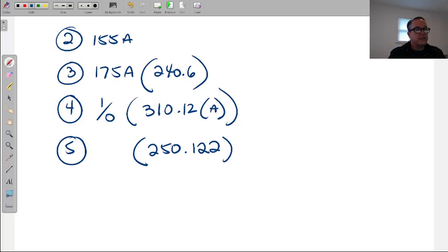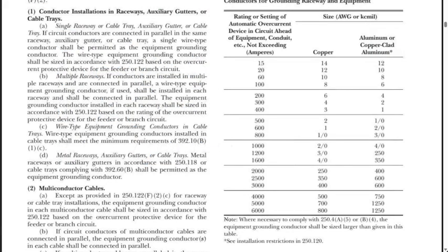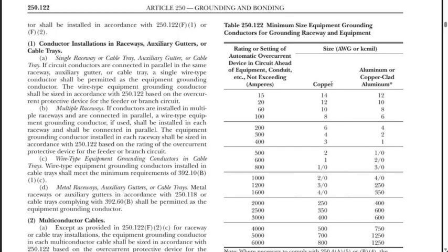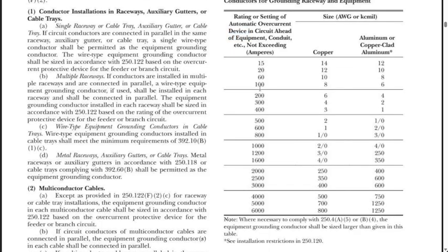And just like the one that I just showed you, 310.12, that says if you have this size main breaker, you're going to use this size feeder conductors or hot conductors. This table, same. Again, we always assume copper unless otherwise mentioned. This table is for minimum size of the equipment grounding conductor. And it gives us the same thing. If you use the overcurrent protection device sized, but now we run into a little problem here. We don't have our 175. The next one up, next page. Exactly. Our next one higher becomes our 200, and so our minimum size for the equipment grounding conductor is number 6.